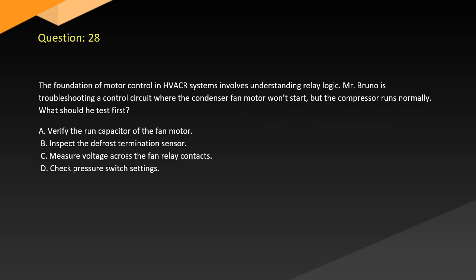Question 28. The foundation of motor control in HVACR systems involves understanding relay logic. Mr. Bruno is troubleshooting a control circuit where the condenser fan motor won't start, but the compressor runs normally. What should he test first? A. Verify the run capacitor of the fan motor. B. Inspect the defrost termination sensor. C. Measure voltage across the fan relay contacts. D. Check pressure switch settings.